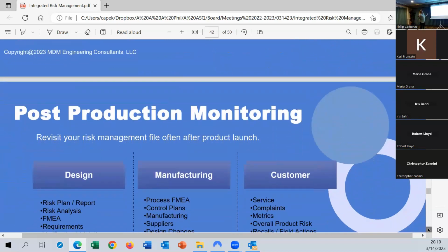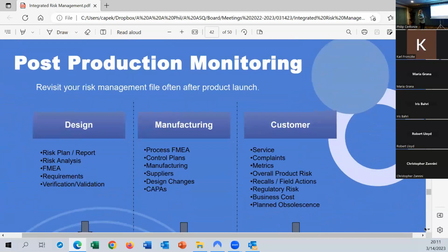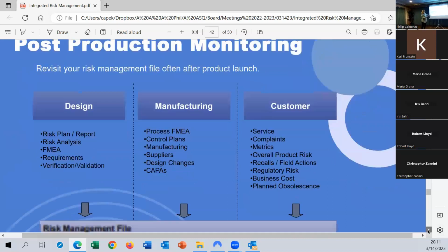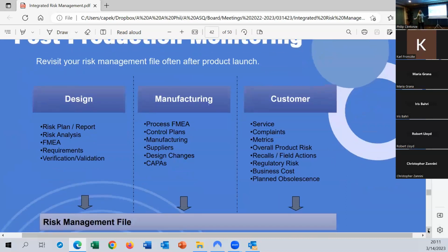Right, so once we've done all our risk work, we create a risk management file. That risk management file is like the repository for all our FMEAs, all our risk analysis, our risk management report. We need to continue to look at our risk file and continue to update it based on design changes, right? If we're making a design change, we need to go back to our risk file. All of these are living documents, so we need to continue to maintain it.